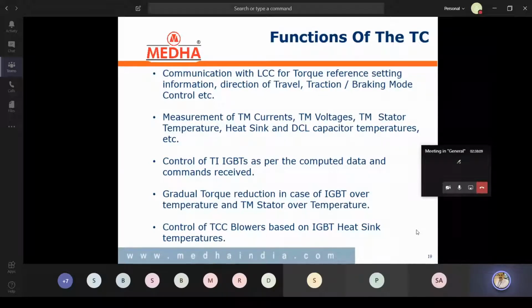Max of all the 6 IGBT temperatures will be taken, and that will be treated as the inverter temperature. And as per the lookup table, one temperature table is there. As per that, the TCC blower will run at 3 different speeds: slow speed, medium speed, and high speed, to get the higher efficiency out of the IGBTs. So for that purpose, there are 6 individual TCC blowers inside the TCC. So these are the main functions of the traction computer.